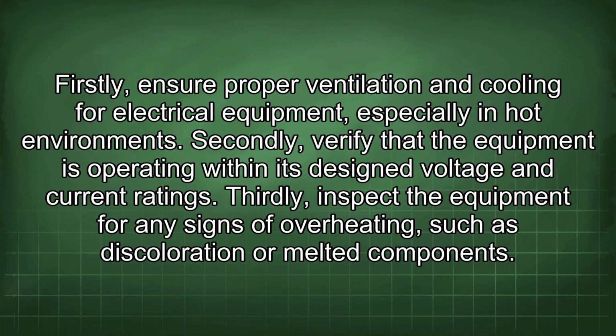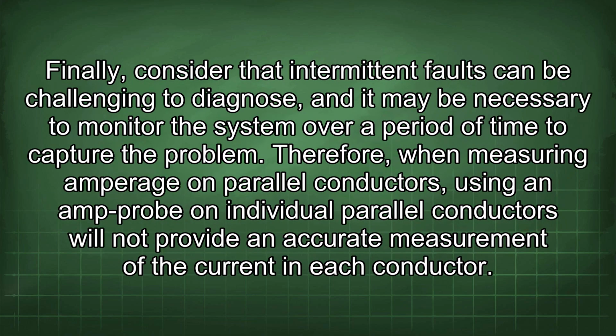Firstly, ensure proper ventilation and cooling for electrical equipment, especially in hot environments. Secondly, verify that the equipment is operating within its design voltage and current ratings. Thirdly, inspect the equipment for any signs of overheating, such as discoloration or melted components. Finally, consider that intermittent faults can be challenging to diagnose, and it may be necessary to monitor the system over a period of time to capture the problem.